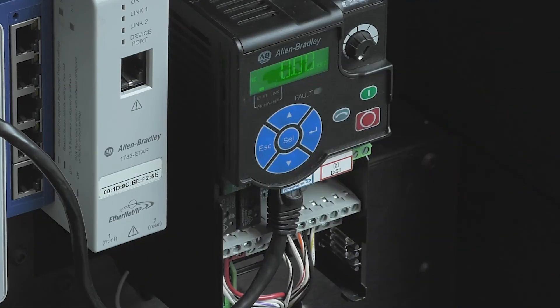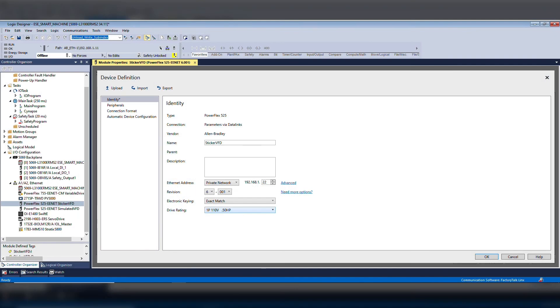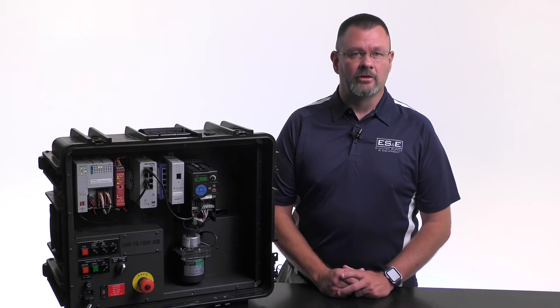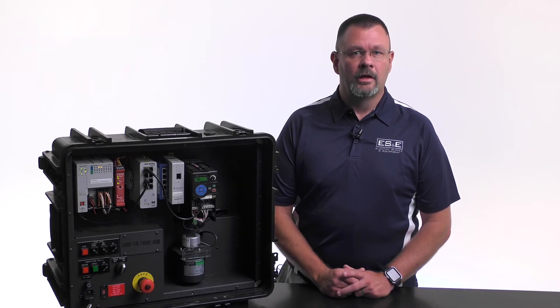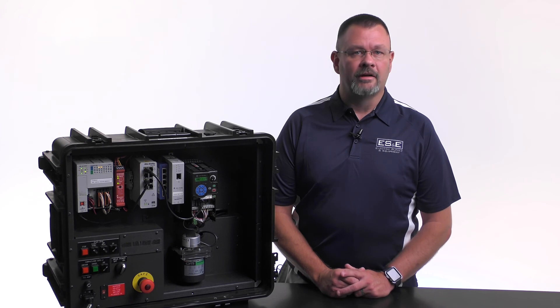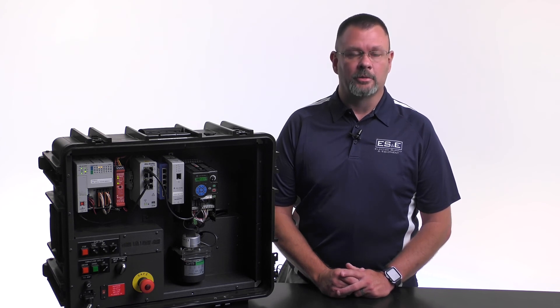To show this in action, we have a drive set up and it is connected to our controller, which is configured for ADC. Here is our module definition set up for electronic keying exact match. This means the drive's firmware and parameters must match exactly the configuration stored in the controller. If the electronic keying was left to the default setting of compatible, the controller does not verify the drive's firmware and only verifies the parameters.